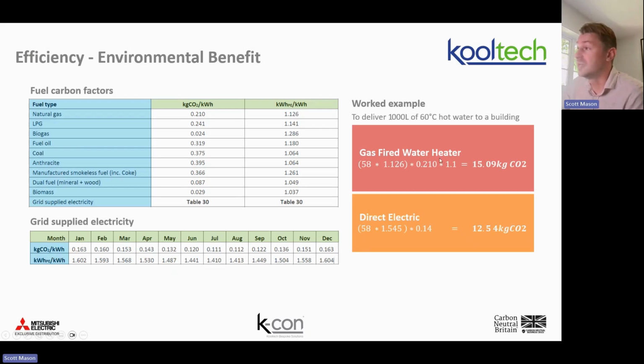A gas-fired water heater delivering 1,000 litres of hot water in an hour is going to take about 58 kilowatts. Or if we could forget the hour bit, it's just going to be 58 kilowatt hours of energy. And at 58 kilowatt hours, primary energy factor, carbon intensity of the energy source, product efficiency, total emissions as a result of basically generating that 1,000 litres at 60 degrees centigrade.